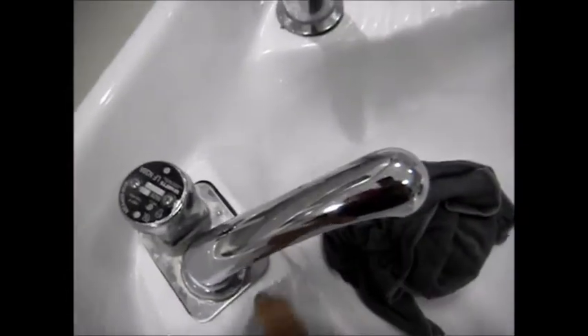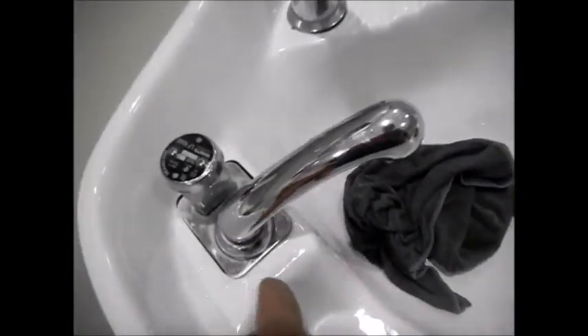It's the same thing here. I just wiped this up, but you can see where it was dripping, and it's not from the fittings — it's from this gasket here. You can see this gasket; there's no sealer put on it. The gasket is not seated squarely.